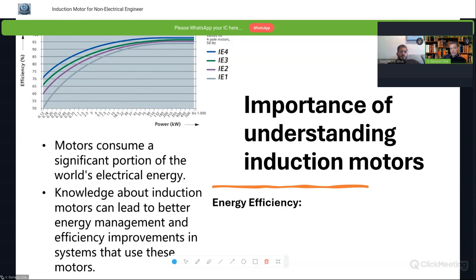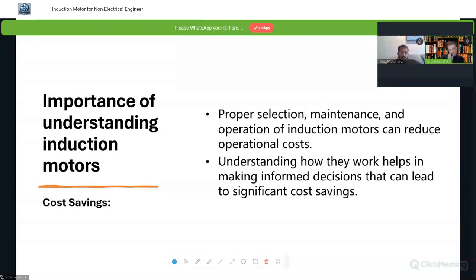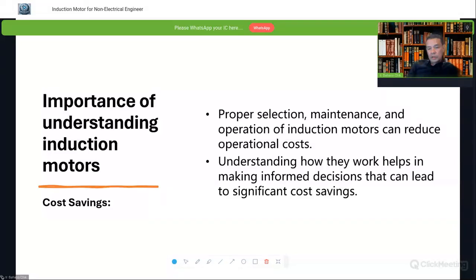These motor efficiencies are tied to the commercial side. If you are looking for highly efficient motors, that means you need to pay more. Normally we go for standard efficiencies, but it depends on the project's requirement. So it is important to understand all the components that make up the motors, and from there, we can develop a good preventive maintenance for the audience involved with maintenance of a plant. In the end, it will lead to reduced operational costs, and finally, it will result in overall cost saving.